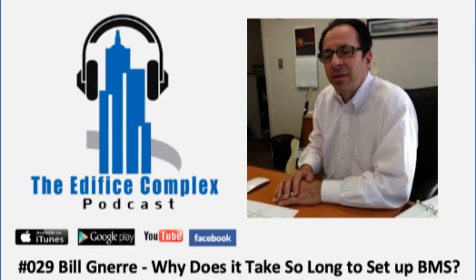Going back to using a tool like Belimo for data acquisition, with a delta T and a flow, you've got BTUs. So if you've got BTUs on a particular air handling unit and you've got weather data, you should be able to compare those and say: the building was designed this way, we selected the air handler this way, this is the load at these weather conditions. Is there congruency? If there is, and everything's running, then you've commissioned that part of the system. If there's no congruency, you have a problem.